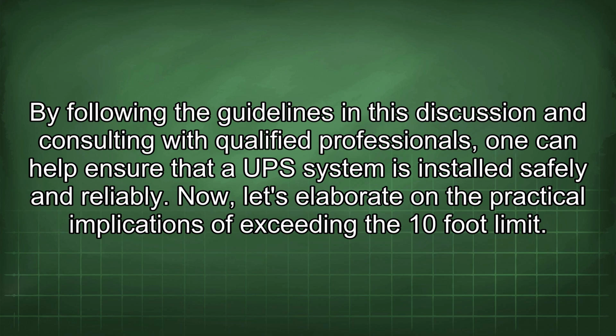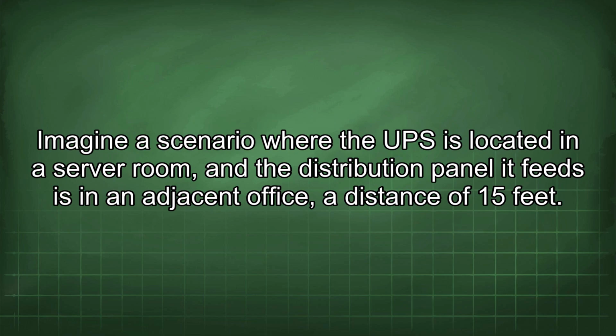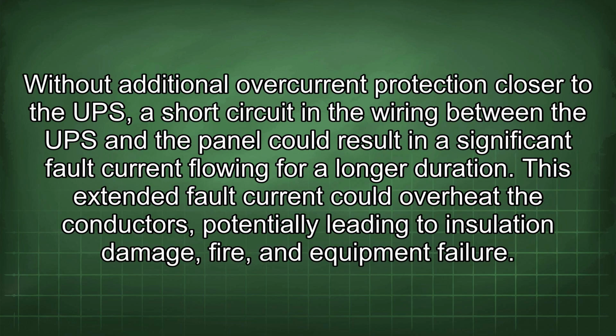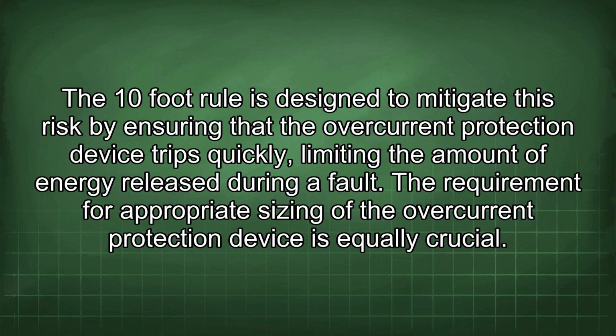Now, let's elaborate on the practical implications of exceeding the 10-foot limit. Imagine a scenario where the UPS is located in the server room and the distribution panel it feeds is in an adjacent office, a distance of 15 feet. Without additional overcurrent protection closer to the UPS, a short circuit in the wiring between the UPS and the panel could result in a significant fault current flowing for a longer duration. This extended fault current could overheat the conductors, potentially leading to insulation damage, fire, and equipment failure. The 10-foot rule is designed to mitigate this risk by ensuring that the overcurrent protection device trips quickly, limiting the amount of energy released during a fault.